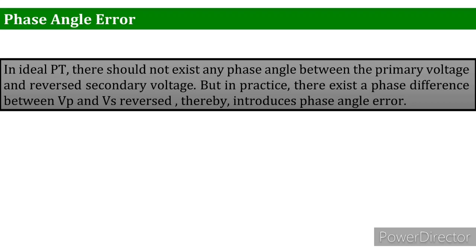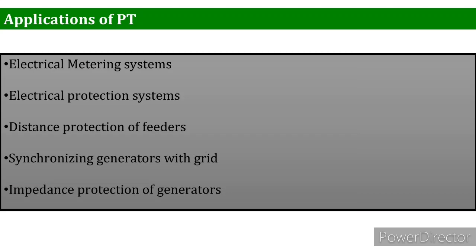To reduce these errors and improve accuracy, the transformer should be designed so that its windings have appropriate magnitudes of internal resistance and reactances. In addition, the core should require minimum magnetizing and core loss components of the exciting current. Some applications of instrument transformers include electrical metering systems, electrical protection systems, distance protection of feeders and transmission lines, synchronization of generators with the grid, and impedance protection of generators. That concludes the instrument transformer section Part 2 on potential transformers.